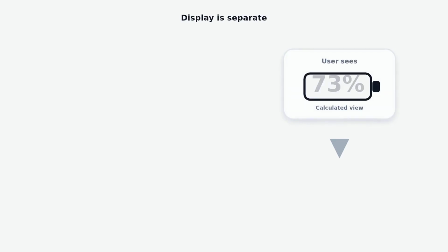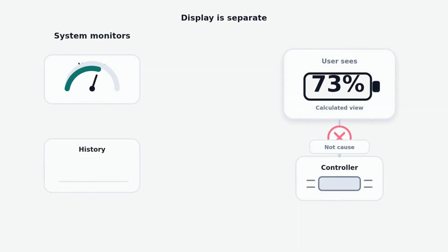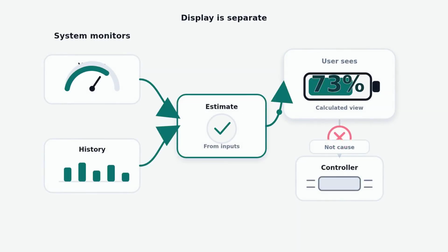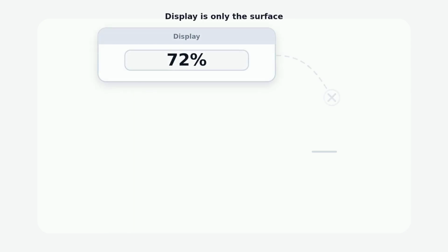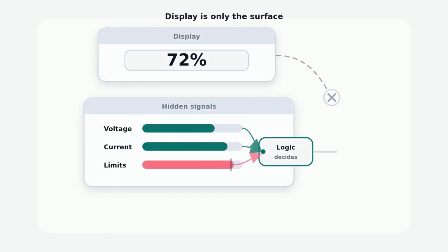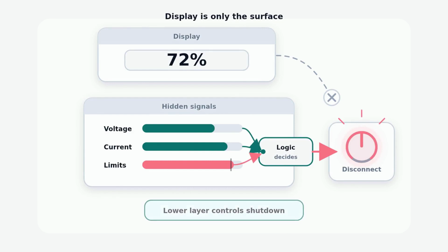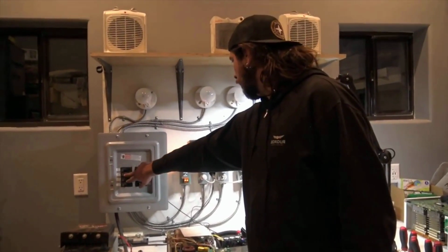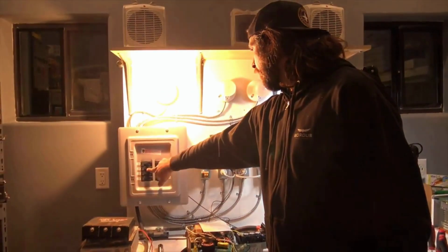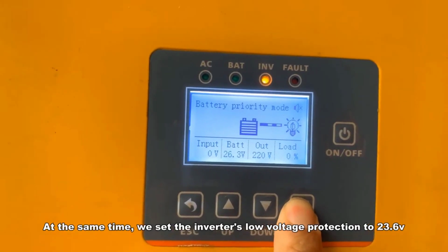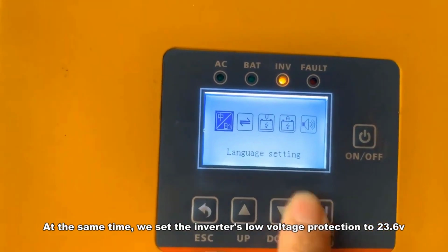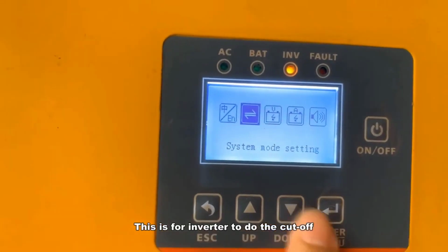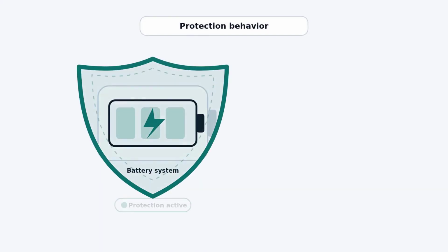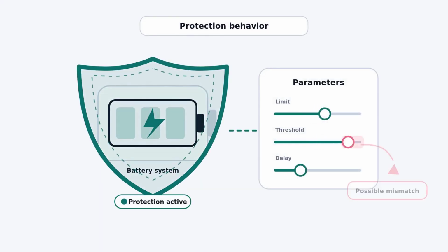The percentage on the display did not cause that. The percentage is an estimate derived from voltage and history. It is not a direct sensor reading. The shutdown is responding to something underneath that number. So before chasing a defective battery or a failed inverter, confirm one thing. Does the system come back after the load is removed? If yes, you have not diagnosed a failure. You have confirmed a protection system doing its job, possibly with the wrong parameters.